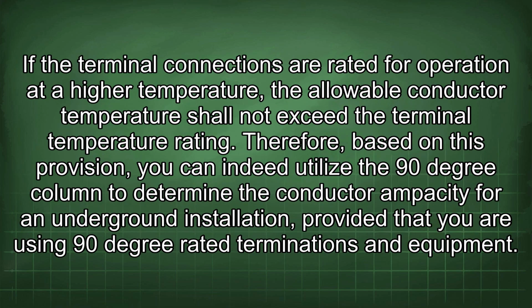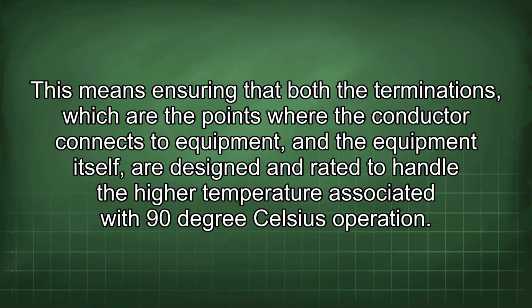If the terminal connections are rated for operation at a higher temperature, the allowable conductor temperature shall not exceed the terminal temperature rating. Therefore, based on this provision, you can indeed utilize the 90-degree column to determine the conductor ampacity for an underground installation, provided that you are using 90-degree rated terminations and equipment. This means ensuring that both the terminations, which are the points where the conductor connects to equipment, and the equipment itself, are designed and rated to handle the higher temperature associated with 90 degrees Celsius operation.